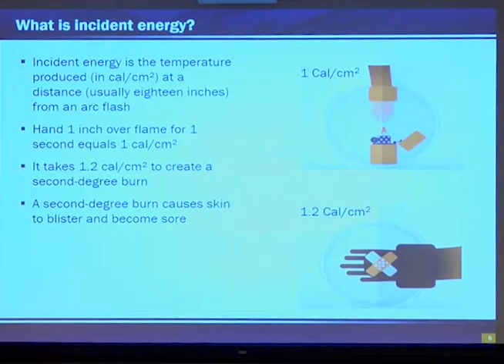Before we start talking about PPE, we need to know what incident energy is. Incident energy is the temperature produced in calories per centimeter squared at a certain distance from an arc flash. If you take a look at the first picture, if you were to hold your hand 1 inch over a lighter for 1 second, that is approximately 1 calorie per centimeter squared. It takes, and I really want to emphasize this, 1.2 calories per centimeter squared to create second-degree burns. Now I turn it over to Mr. Olivo.